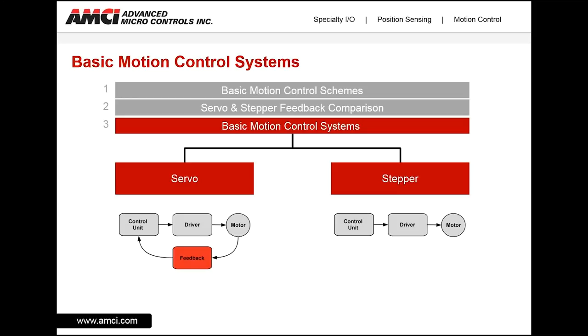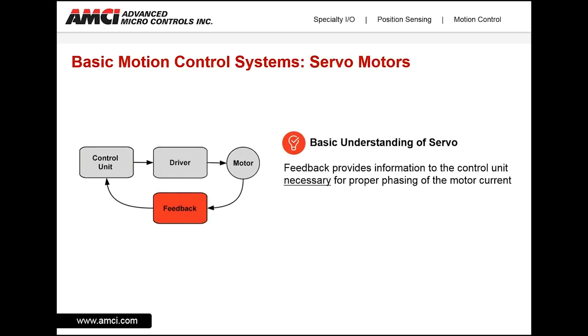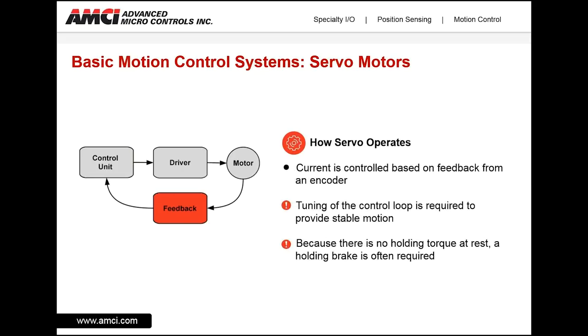Focusing on these two specific motion types, let's look at how each fits into their respective control scheme, starting with a servo. In a servo system, feedback provides information that is necessary for the proper phasing and control of the motor current. Based on commands from the control unit, the driver supplies the motor current, which is continually adjusted based on motor feedback. For proper motion, the system must be tuned. Because there is no holding torque at rest, a holding brake is often required, specifically for vertical applications.